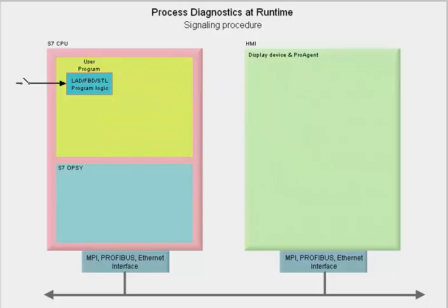As mentioned before, the S7-P-Diag option package generates the functions and instance data blocks for this configured address monitoring. The first function block has the task of monitoring the address in its setpoint state. The second function block stores, at the time of fault, the state of all the signals that make up the result of logic operation of the address being monitored. The fault recognition FB monitors the addresses in the cyclic program in the user block for which the monitoring has been configured.